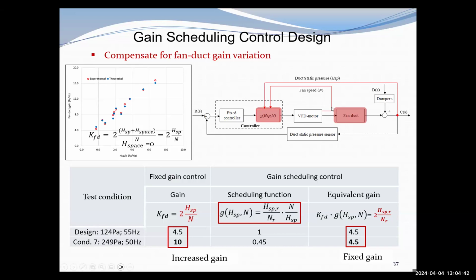Actually, the one advantage of this gain scheduling controller is that the scheduling variables are duct static pressure and fan speed. Right now, for all the buildings, we already installed the duct static pressure sensor to control the supply fan speed. And the fan speed can be readily available from the VFD, right? These two scheduling variables mean we don't have to install additional sensors. It's already there. And if the controller is a programmable controller, then we can directly input this scheduling function into the system to implement it.